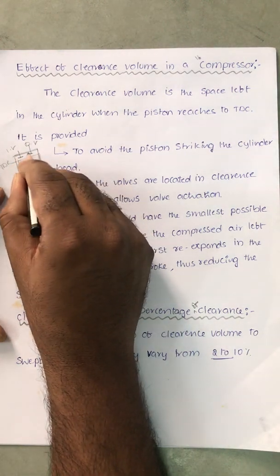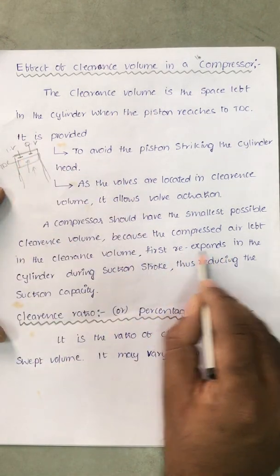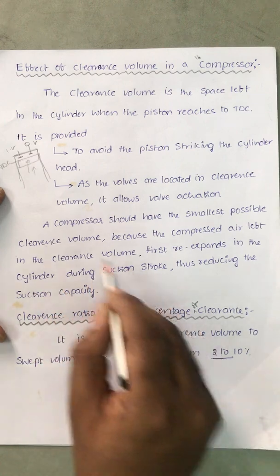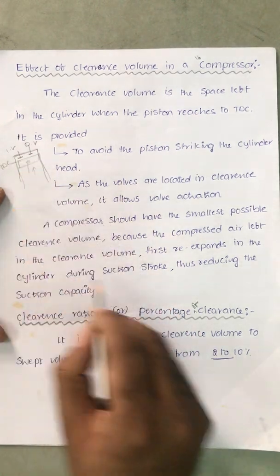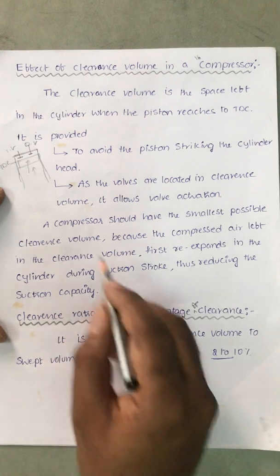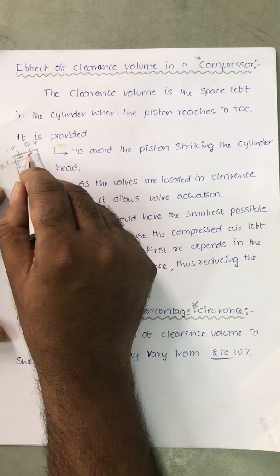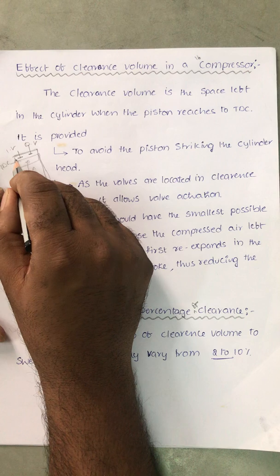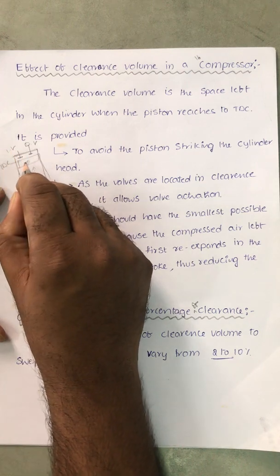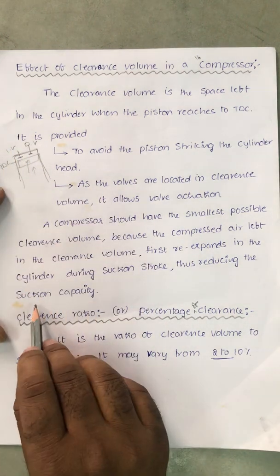During suction, when the piston starts to move downward, the air available in the clearance volume first re-expands. So during the suction stroke when the piston is moving downward, this air expands, thus reducing the suction capacity. Some amount of volume in the cylinder is occupied by the compressed air itself, so the incoming air is disturbed and it automatically affects the suction capacity.